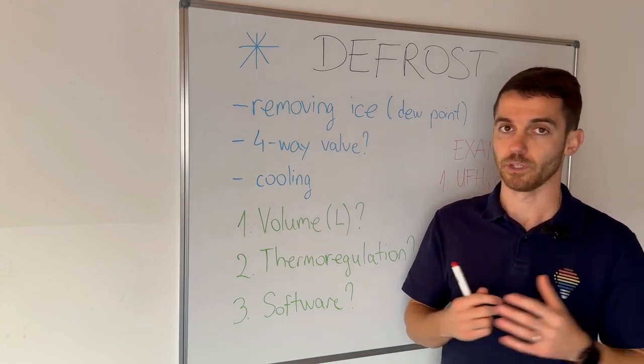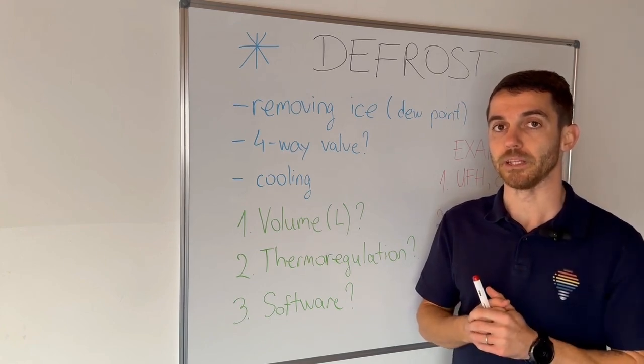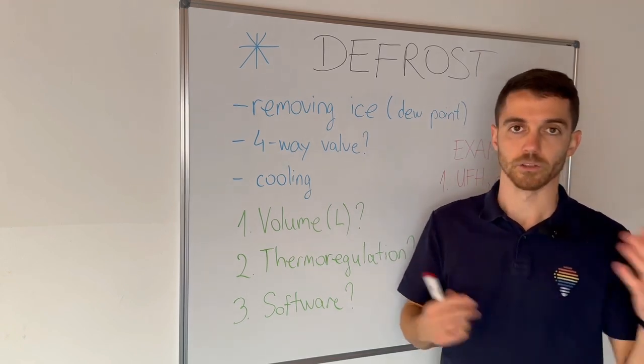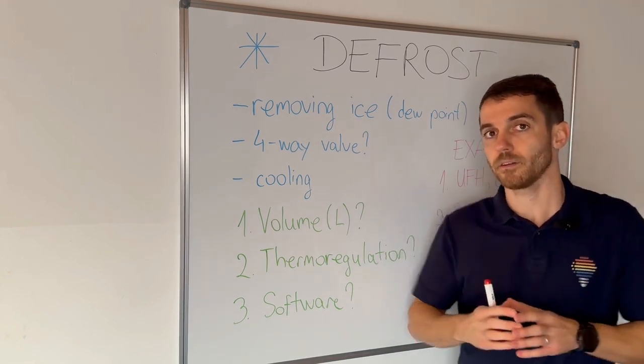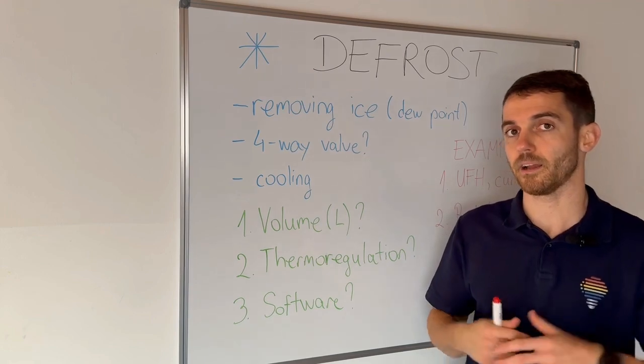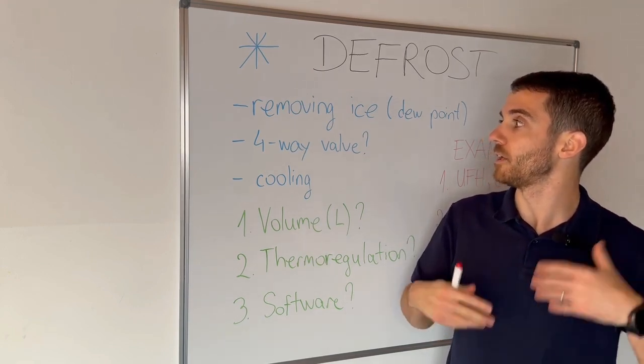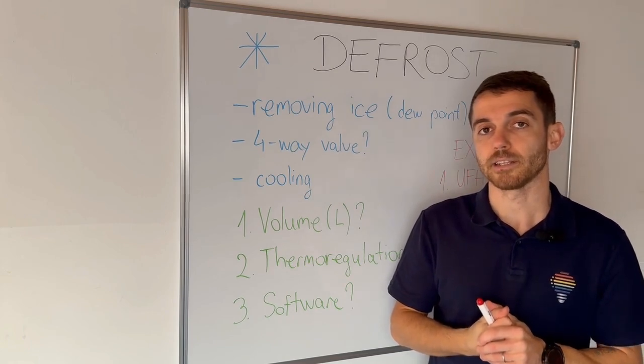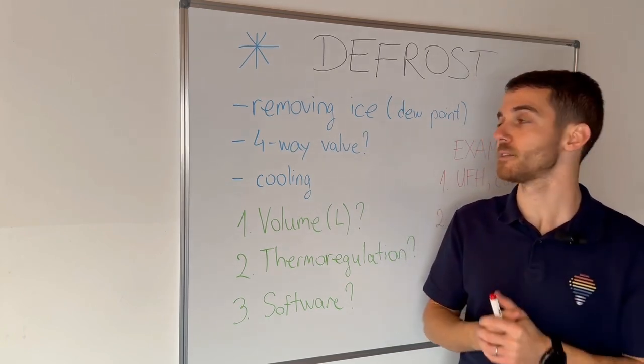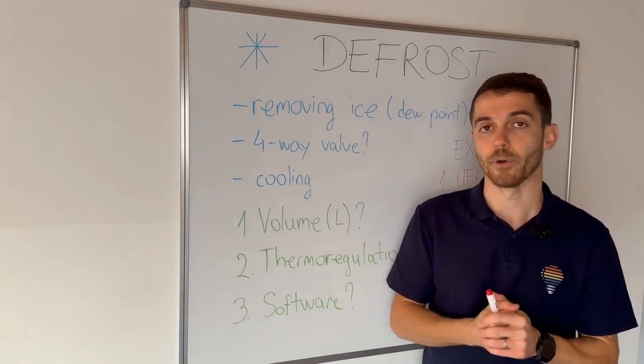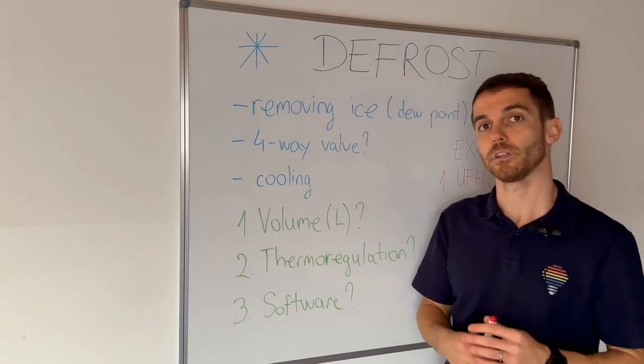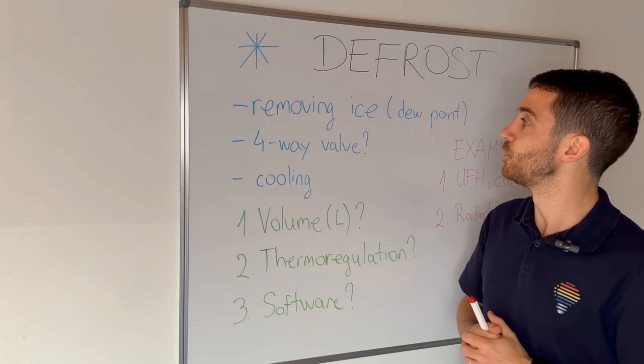It will usually be around zero degrees when humidity is really high in the outdoor air, but depending on the region, country, or city. There is always some humidity in the air, and when this humidity is high and we are extracting heat or cooling our outer unit, we get ice build-up on our evaporator. So we need to remove this ice — at that point, we start the defrost cycle.